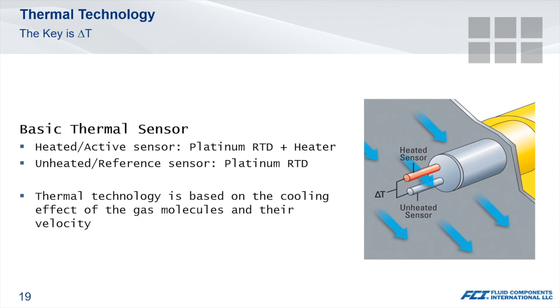The operating principle revolves around differential temperature. One of the RTDs is heated, commonly referred to as the active sensor. The other RTD remains unheated and is known as the reference, since it is measuring the temperature of the process. Measurement is determined by the cooling effect of the active RTD by the gas molecules. A common misconception is that the reference RTD is measuring the heat dispersed from the active RTD. This is not the case.